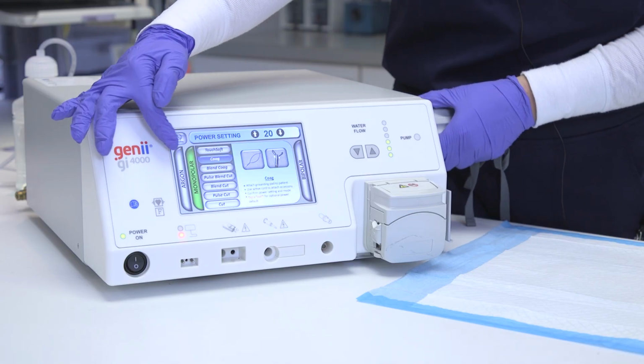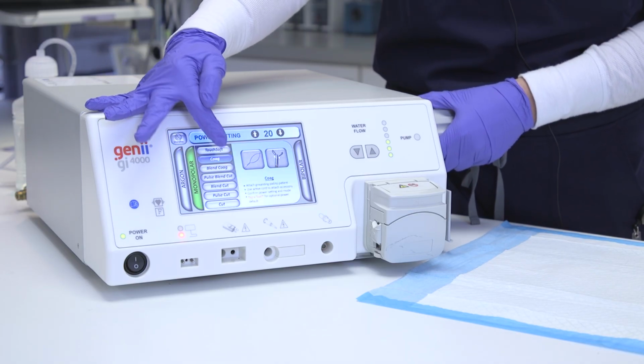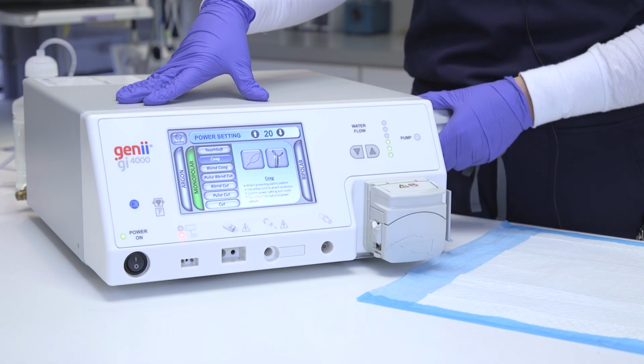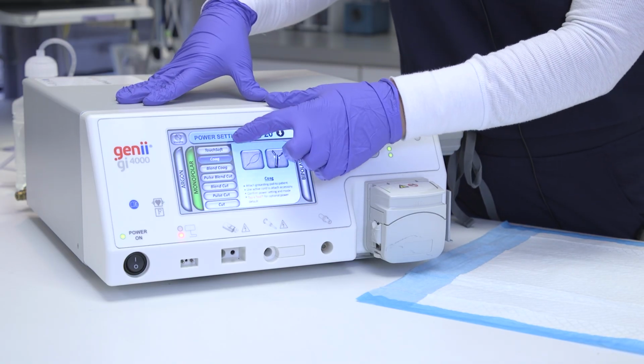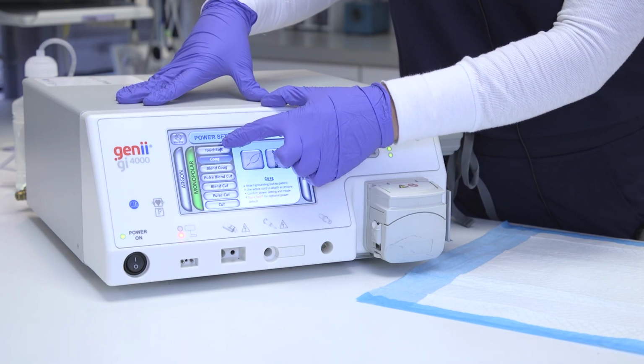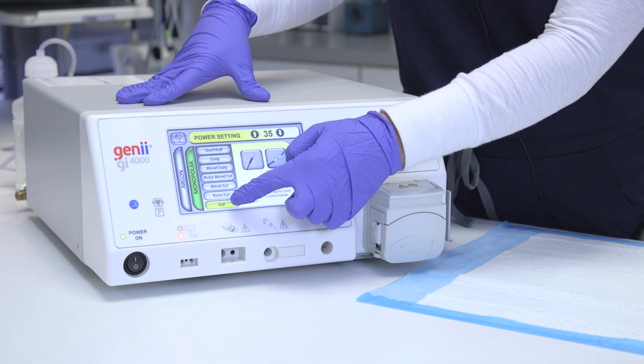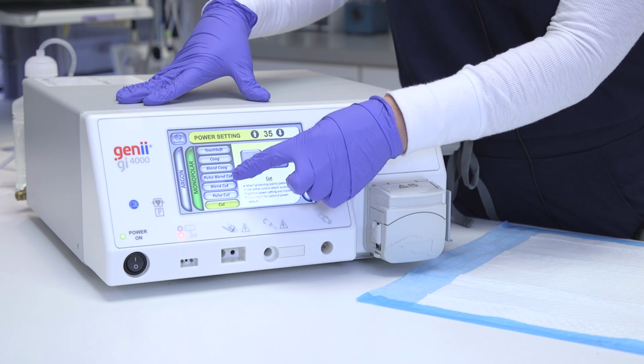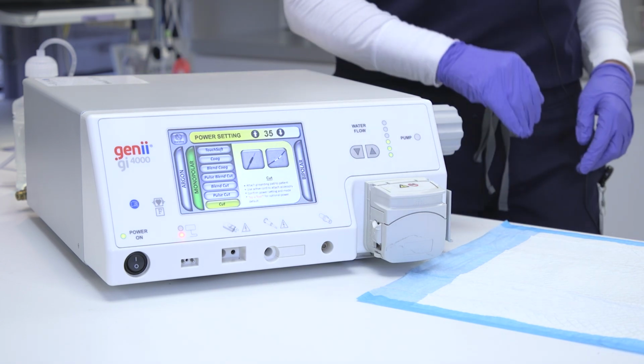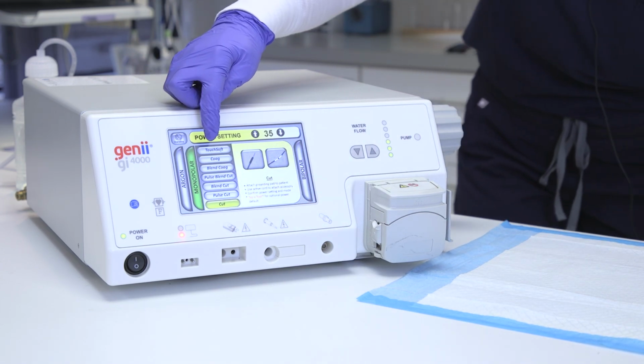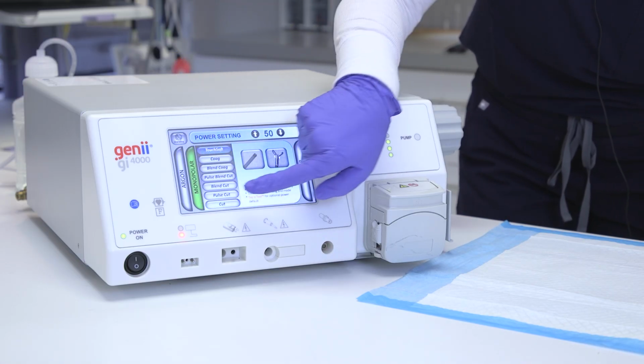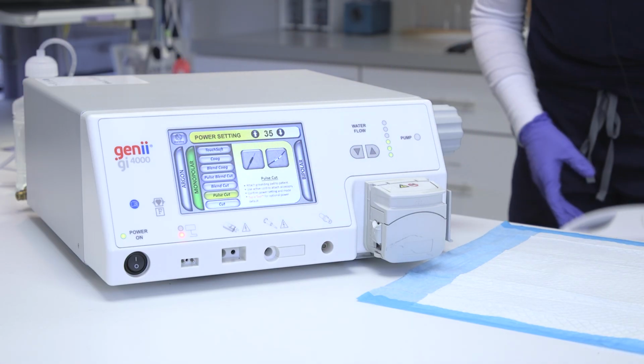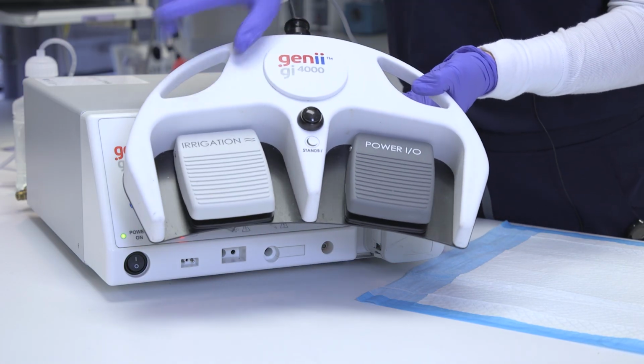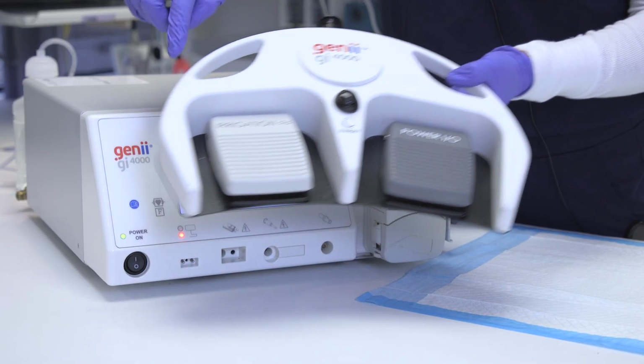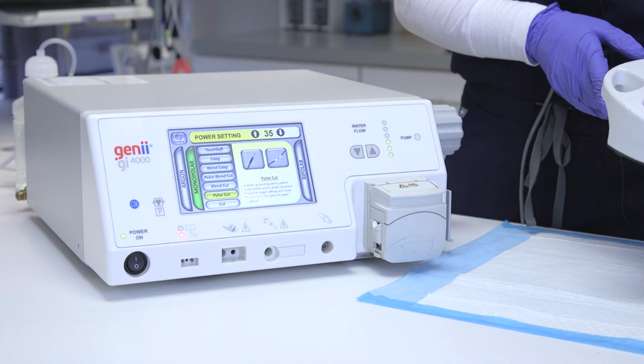The first thing that the unit powers onto is Monopolar coag for your everyday standard polypectomy procedures. We have 7 different modes in Monopolar, ranging from touch soft down to cut, and all the blended waveforms in between. You'll notice on the screen that it goes from blue to yellow. We changed the foot pedal to be power and water so that the cut and coag is now selected on the screen.